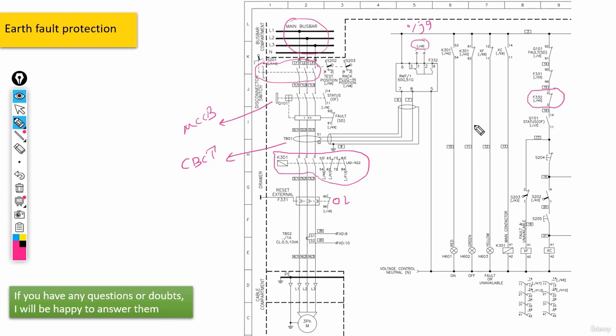So guys, when the CBCT transformer gave us a signal, the earth fault relay would be activated. More specifically, its normally closed contact would be opened. And as a result, the signal to the contactor would be cut off, and well, obviously, the contactor would stop working. Alright guys, so basically, this would be how exactly you can use equipment such as the CBCT transformer and also earth fault relays regarding the matter of earth fault protection in three-phase motors.